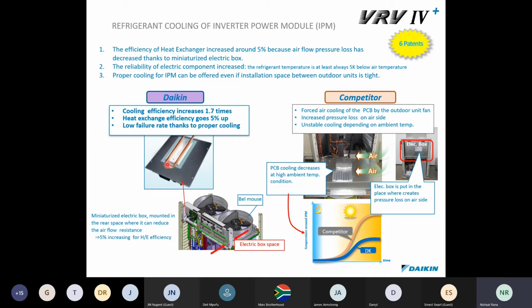If you look at our electronics, why do electronics fail most of the time? Think about these machines sitting outside on a roof or on a floor area or wherever the case may be. They're absorbing direct sunlight and high humid air. Obviously, these electronics do take a knock. Electronics like to be kept cool, around 25 to 26 degrees; that's what they like, or the maximum they can handle. Think of your server rooms. Why do you cool a server room? Because you want to cool the electronics, which give off heat. So what Daikin has done, and we've done it before but we've just increased its efficiency, is provide a cooling circuit to our electronic boards to make sure that the electronics are always cool.